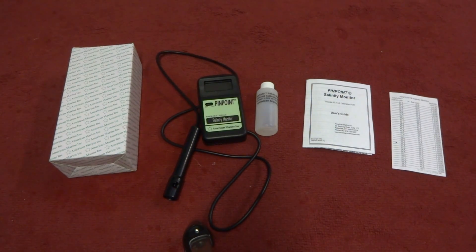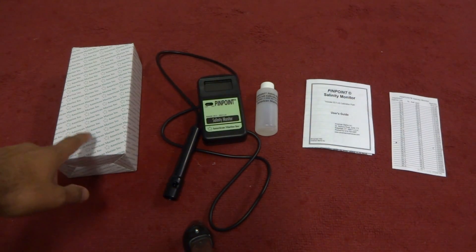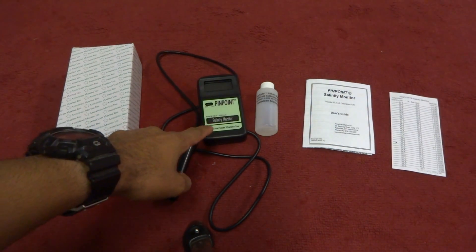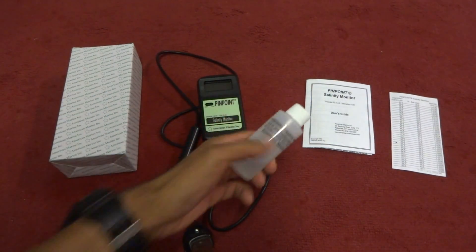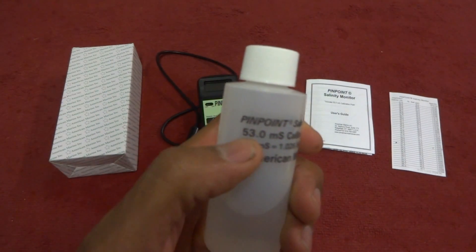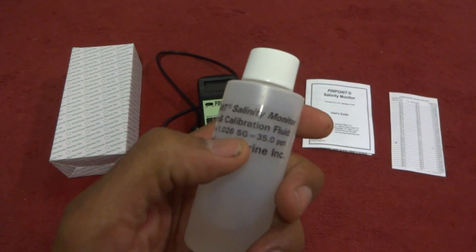When you purchase the Pinpoint Monitor you get the box that it comes in, the monitor itself, calibration fluid which the target number is going to be 53 mS or 35 parts per thousand.